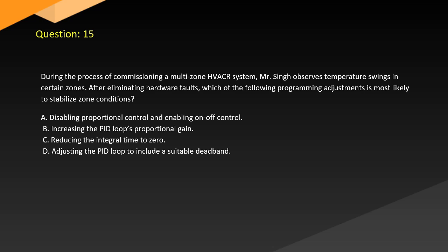Question 15. During the process of commissioning a multi-zone HVAC system, a technician observes temperature swings in certain zones. After eliminating hardware faults, which of the following programming adjustments is most likely to stabilize zone conditions? A. Disabling proportional control and enabling on-off control. B. Increasing the PID loop's proportional gain. C. Reducing the integral time to 0. D. Adjusting the PID loop to include a suitable deadband.